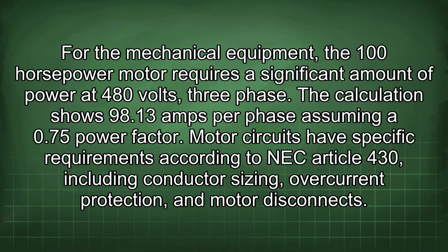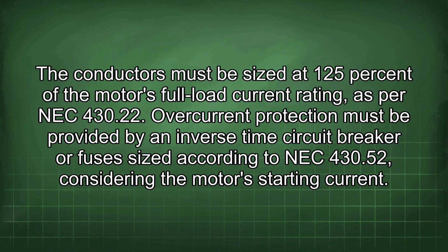For the mechanical equipment, the 100 horsepower motor requires a significant amount of power at 480 volts, 3 phase. The calculation shows 98.13 amps per phase, assuming a 0.75 power factor. Motor circuits have specific requirements according to NEC Article 430, including conductor sizing, overcurrent protection, and motor disconnects.